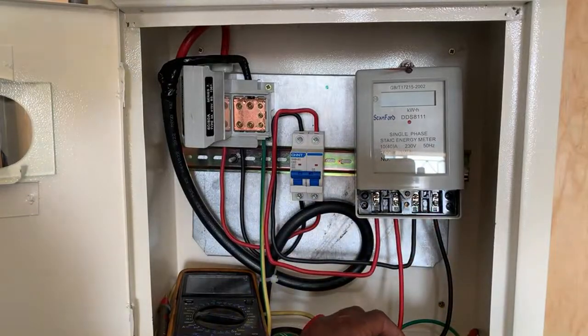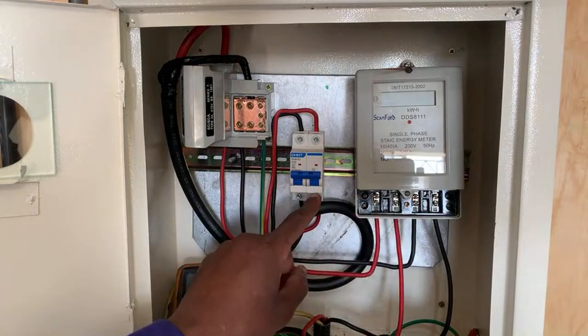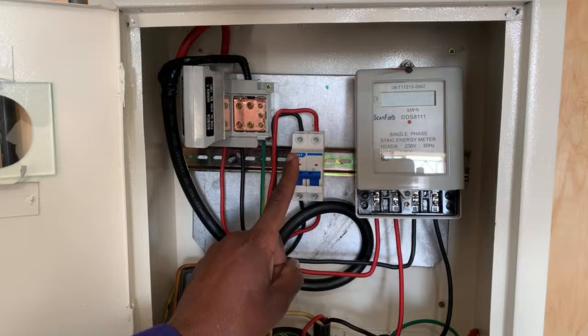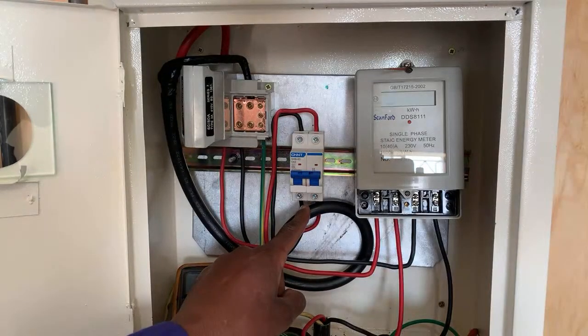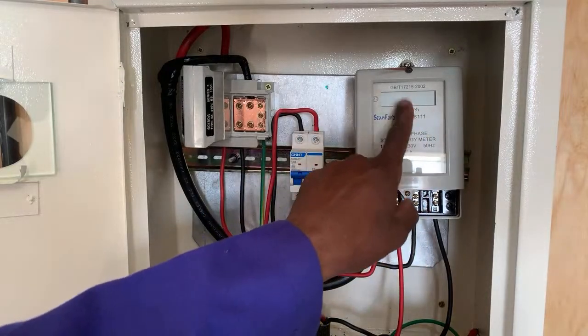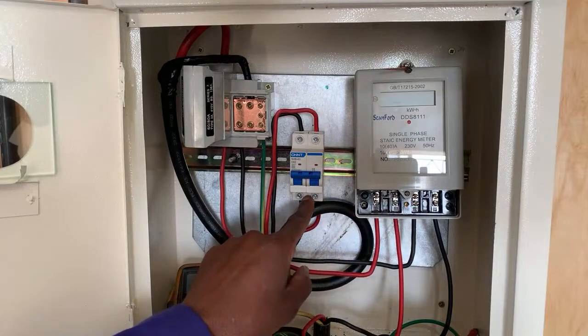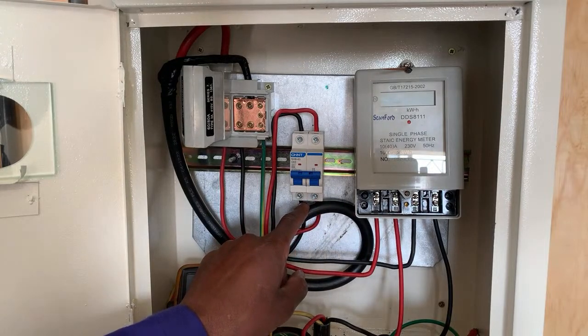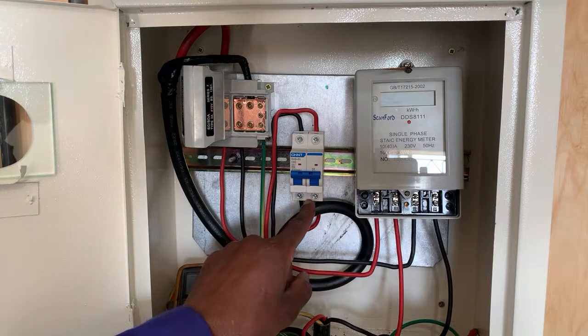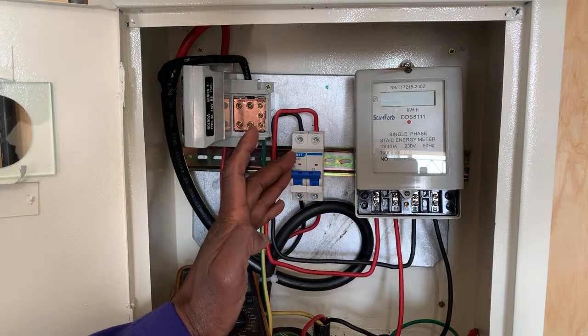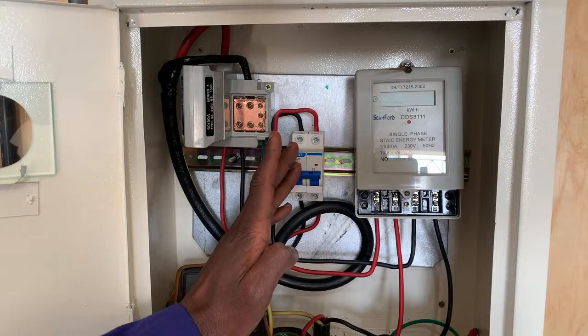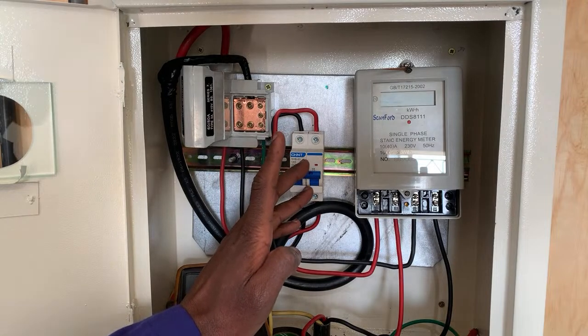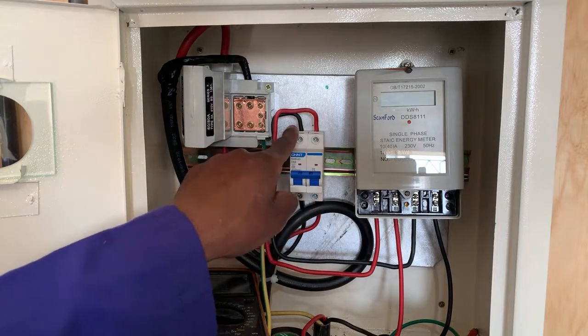And before we go to the energy meter, there's another issue that may happen as well. Let's say this double pole switch is on, but the customer does not have electricity and the energy meter is off. Another likelihood is that the fault is at this particular point, where you will have this cable or this connection charred, or burned out due to loose connections. When such an event happens, that connection is not allowing easy flow of electricity from the double cutout to this double pole, and it does not give an output here.